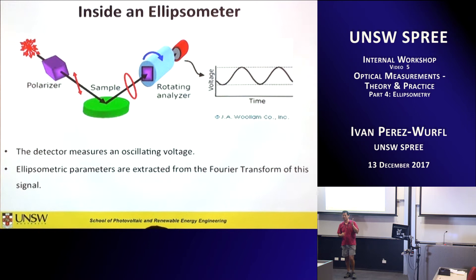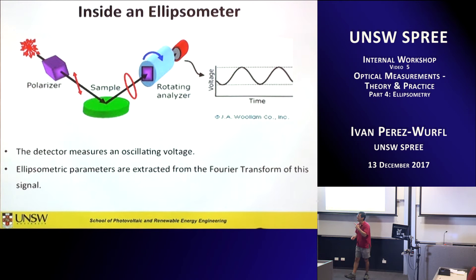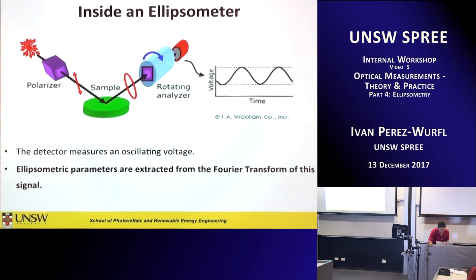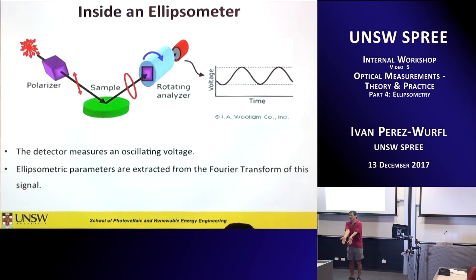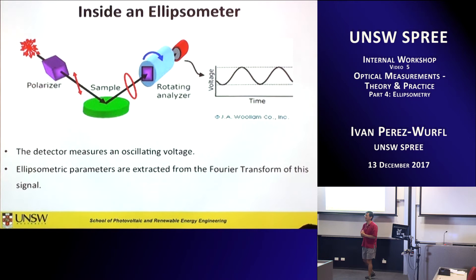On one side of the ellipsometer you have the polarizer. For this particular instrument, it uses linearly polarized light for the input, at 45 degrees, so you get exactly the same amount of S and P coming in. On the other side you have the analyzer, which is essentially a polarizer that is rotating. As the polarizer rotates, you are looking at the amplitude of the polarization vector. It forms a sinusoidal wave that you fit with a Fourier transform, and from there you get the offset, peaks, and valleys — from which you extract the information.